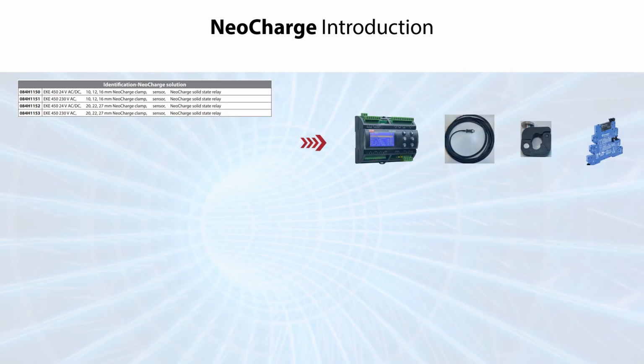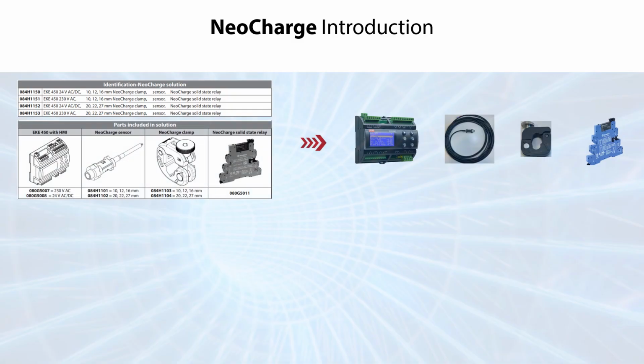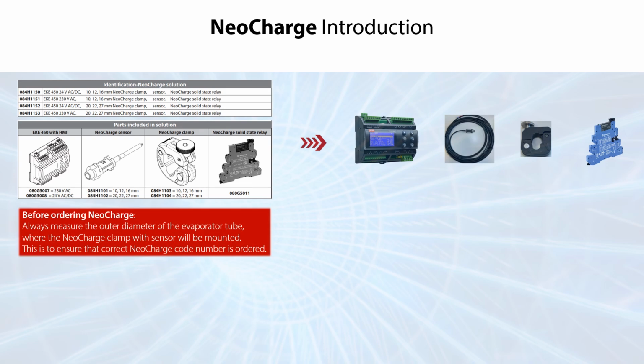Which code number to order and use depends on the given power supply and given outer diameter of the evaporator tube as specified. As also seen here, the different parts included also have separate code numbers and can be ordered separately as spare parts. Please note that before ordering the Neocharge, always measure the outer diameter of the evaporator tube where the clamp with sensor will be mounted. This is to ensure that the correct code number is ordered. You can also see more about this later in this video.